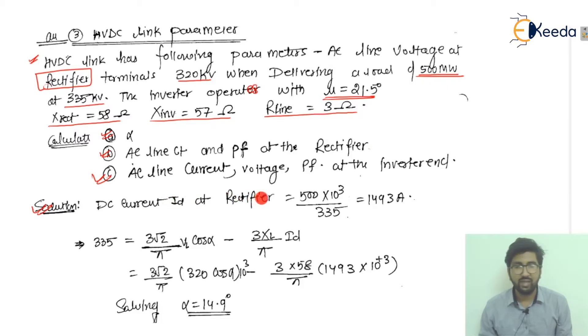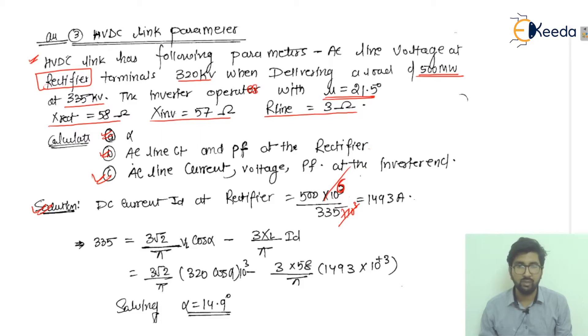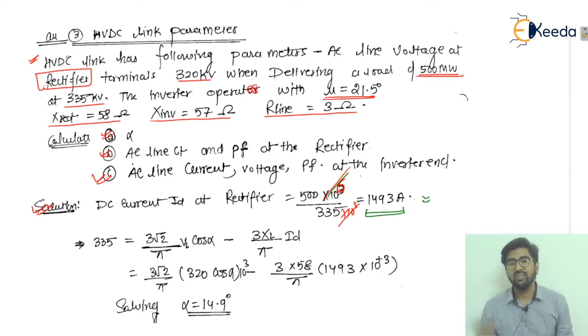DC current ID at the rectifier side is simply power divided by voltage. Power is 500 megawatt and voltage is 335 kilovolts, so ID = 500×10⁶ / 335×10³. After simplification, that is 500/335 multiplied by 1000, giving us 1493 amperes.